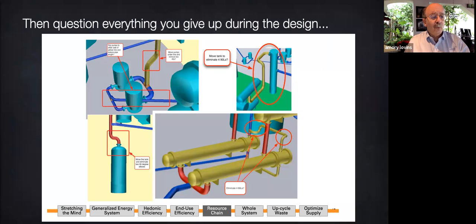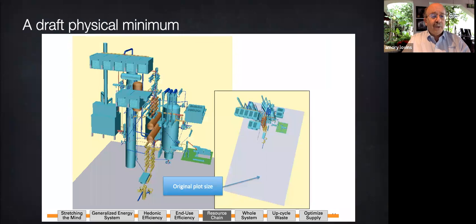Look at the lower right diagram's lower left end. Where's the Y joint? And underneath at the far right, maybe that connector could just run in a big arc and eliminate two elbows. Now, always elbows to get rid of. Now, the result of that first pass at untangling the pipe spaghetti was much simpler and several folds smaller. Look at the enormous shrinkage in the footprint.